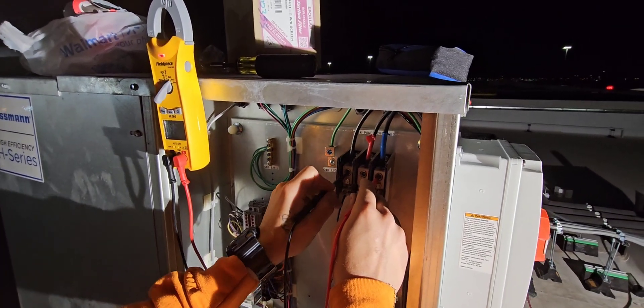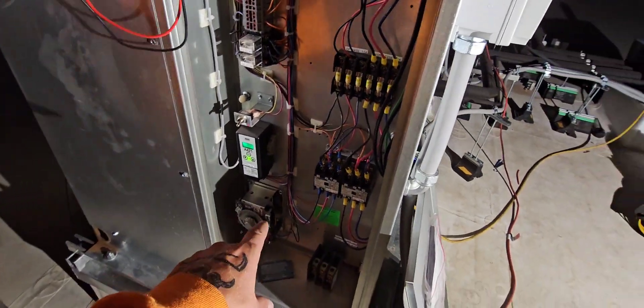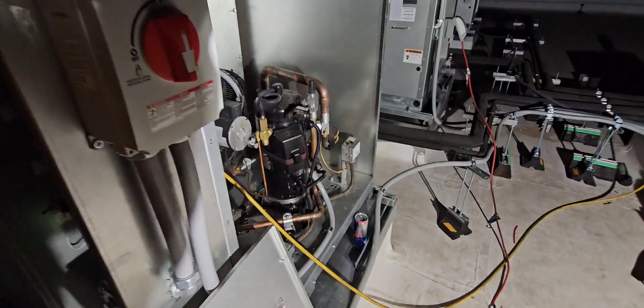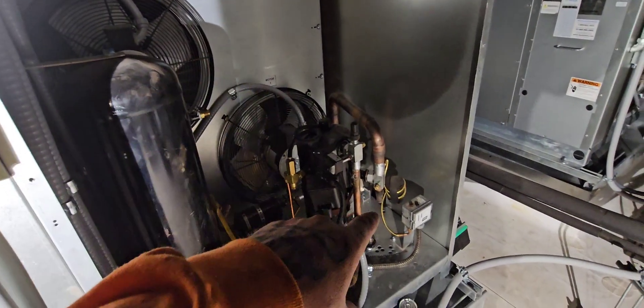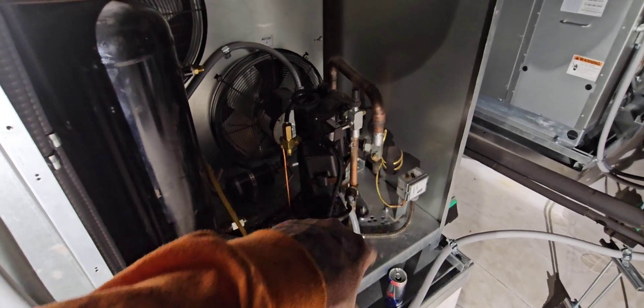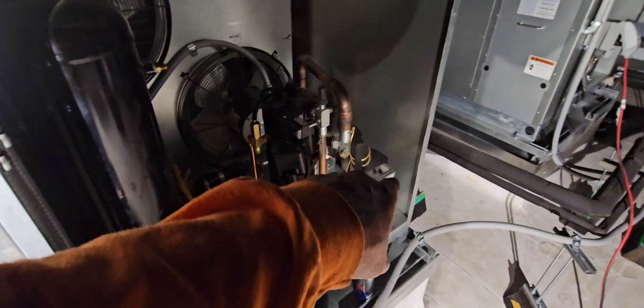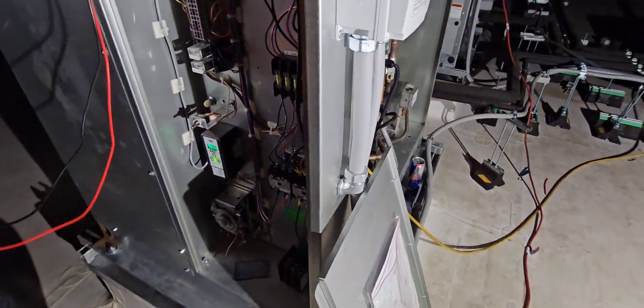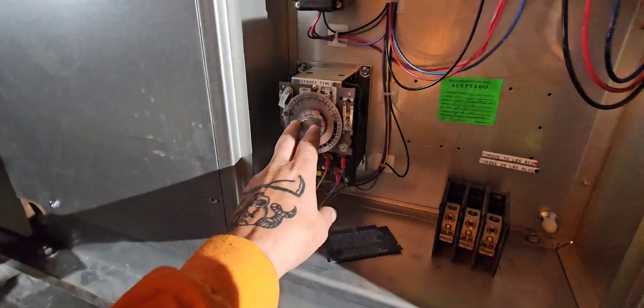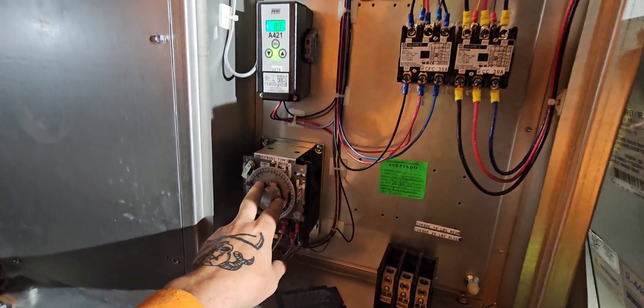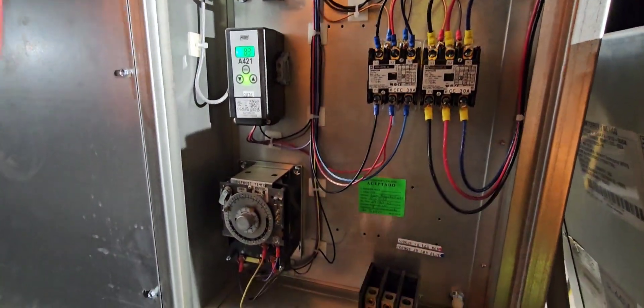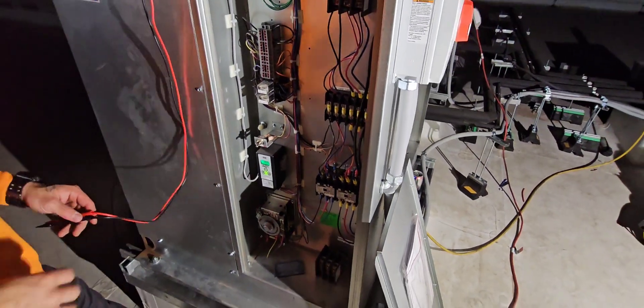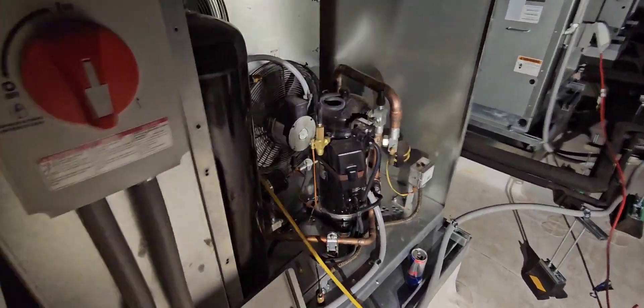208 across all three. Basically how this thing is going to run, because we have those ke2s, the ke2 is controlling the solenoid downstairs. So basically the condenser fans and compressor is just going to run off of the low and high pressure control. The ke2 will energize the solenoid, build pressure, close that low pressure control, kick the compressor and condenser fans on. And then when it pumps down it'll turn them off. This defrost clock, this pump down switch is out of play. You could run this thing standalone just with that defrost clock, but we're going to go back downstairs and start charging this thing up.